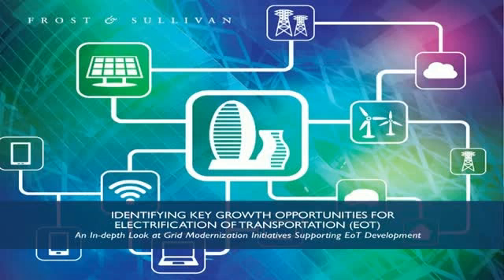This poses a serious problem to the local distribution transformer network. Based on our research, there are several studies that highlight this problem. The table on this slide clearly illustrates the depreciation rate of a local distribution transformer as a result of an additional EV connected to the grid. With just two additional EVs connected to a local distribution transformer, the average annual depreciation rate, particularly during peak times, will go up from 0.6% to 9.6%.